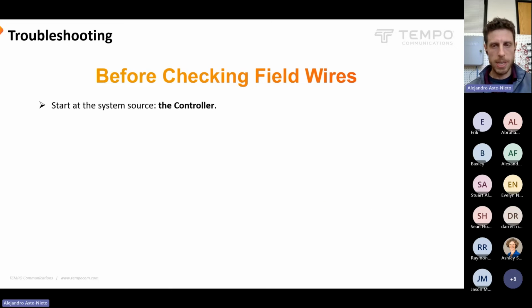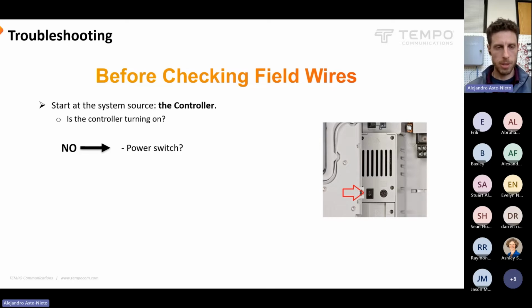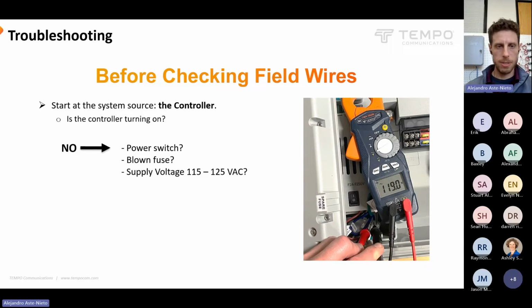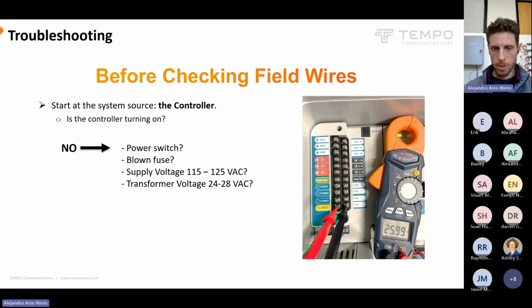So when we begin our troubleshooting process, obviously we want to start at the controller, and it can tell us a lot of information. For one thing, is it able to turn on? If not, let's check for anything obvious. Power switch: did that somehow get flipped? Did a fuse blow? Is the supply voltage correct? Is the transformer working correctly? Is the voltage coming out of there within our range? If all that checks out, let's see what's going on in the wire path that might be introducing some problems.